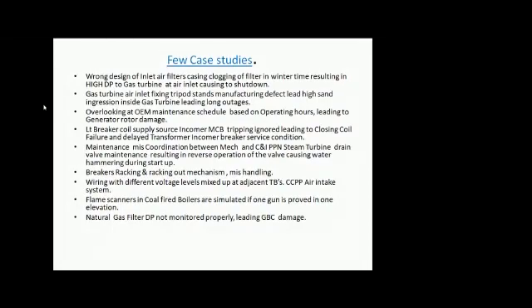Operators apply different amounts of force with their hands while racking in, racking out, because everybody has their own wrist power, muscle power. So while racking in, racking out, they apply different kinds of pressure. The breaker has to be properly maintained, and the operator has to be trained properly so that he does not give any undue pressure while racking in, racking out. If something is not coming out, you should immediately inform the maintenance man that something is wrong. You should not apply overpressure onto the equipment while racking in, racking out. This can cause damage which may lead to long shutdowns.